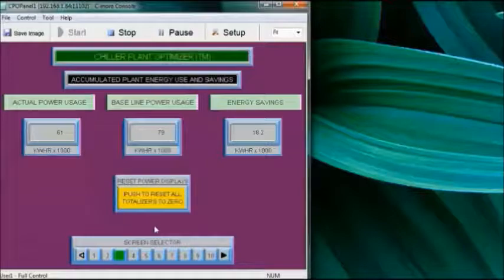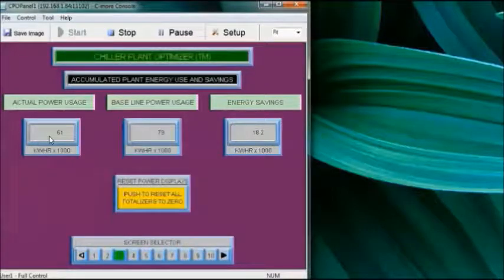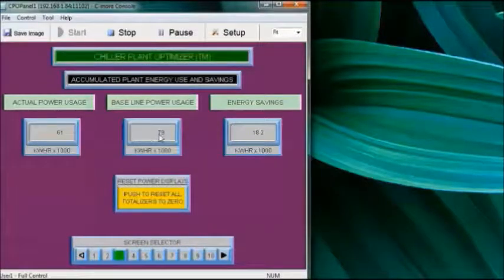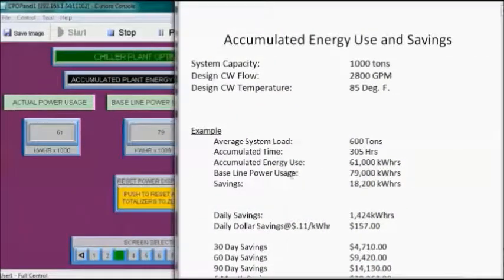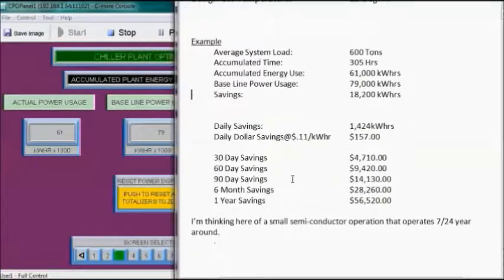We would also like to see how the optimizing strategies are working. This screen captures the information to let us know. Over this period of time, we have used 61,000 kWh. The baseline power usage without optimization would have been 79,000 kWh, and thus we have a savings of 18,200 kWh. We can reset this all back to zero. We've accumulated these savings over about 305 hours, which translates into a daily savings of over 1,400 kWh. The daily dollar savings at 11 cents per kWh would be $157.